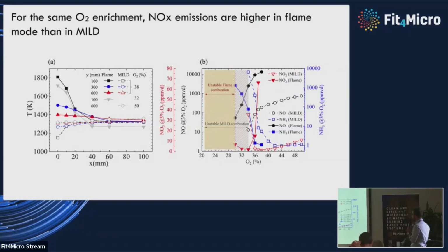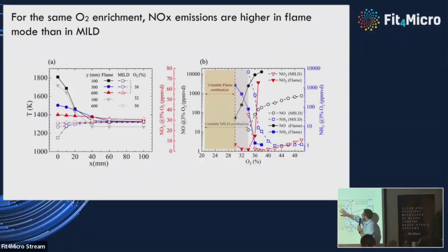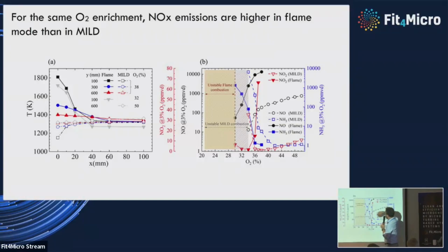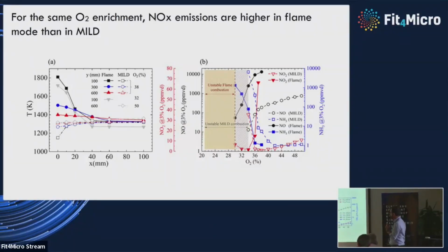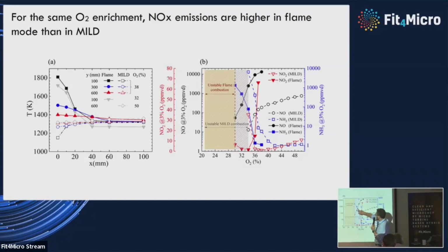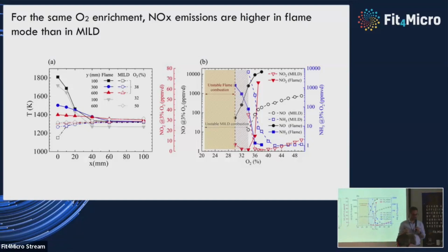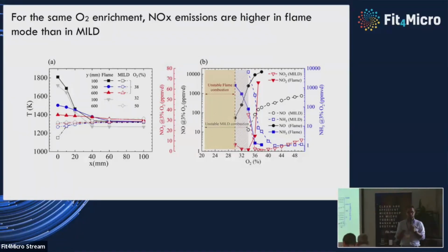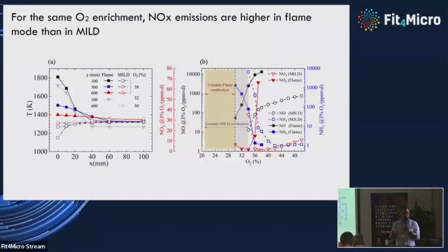The question is what you can do to lower these emissions. When you use standard flame conditions, there's a trade-off between ammonia slip and NOx emissions, located at very large values of both — around 800 ppm. Why call it a trade-off? Because you don't want very low emissions at the cost of emitting ammonia. Emitting ammonia in the exhaust would mean you're not even burning your fuel properly.